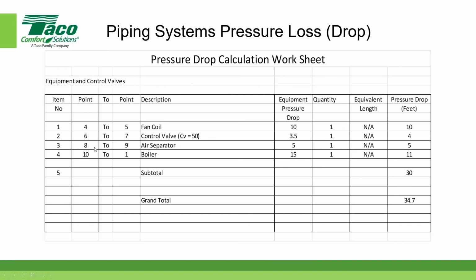The air separator was point 8 to point 9, and again, the only place I can get that pressure drop is from the manufacturer. In this case, it's 5 feet. And the boiler is point 10 to point 1, which brings us right back to the beginning. And again, the only place I can get the pressure drop for that is from the boiler manufacturer. So there I have the values for all of the equipment and the control valve.